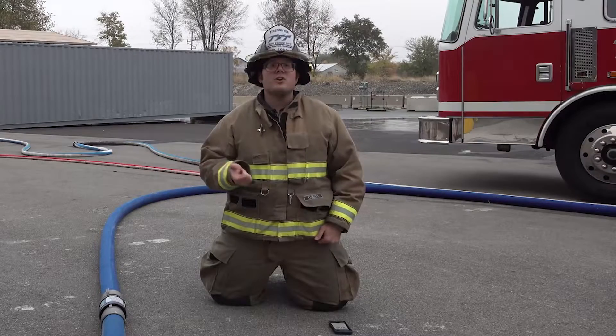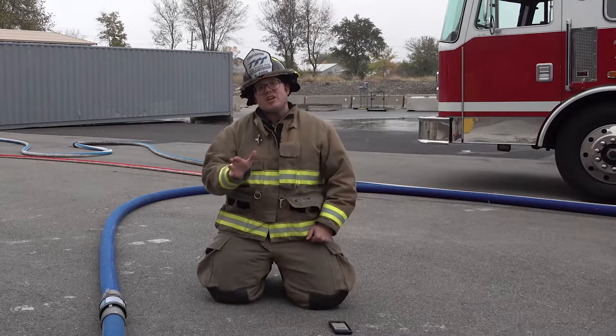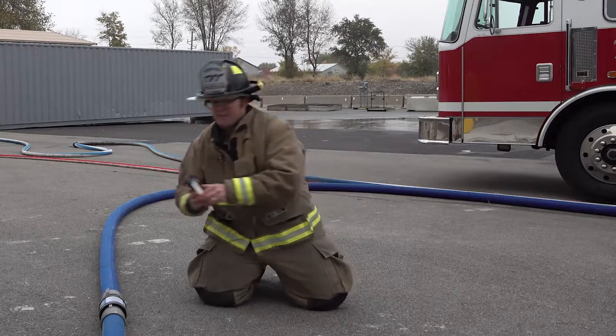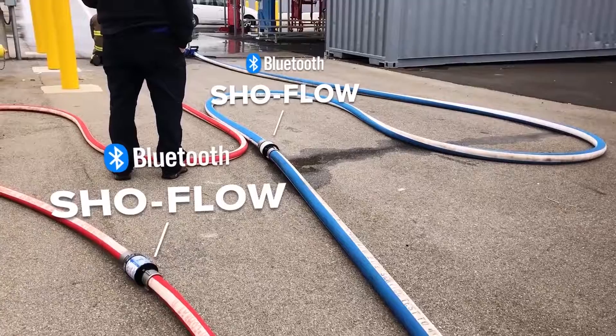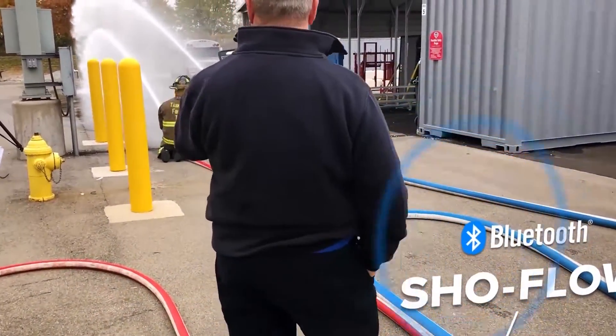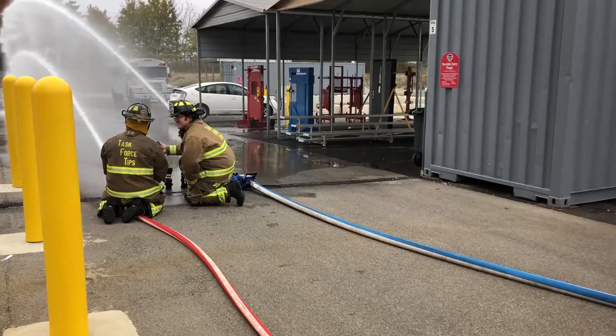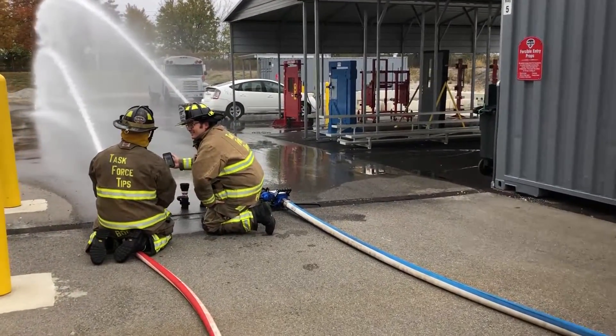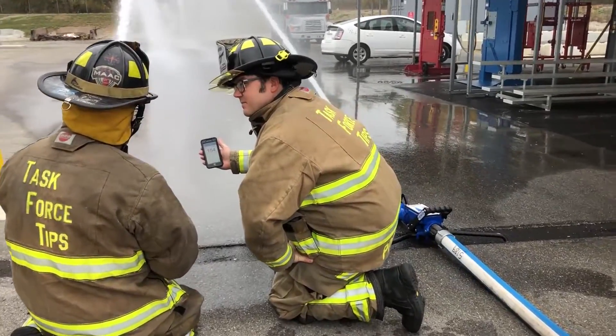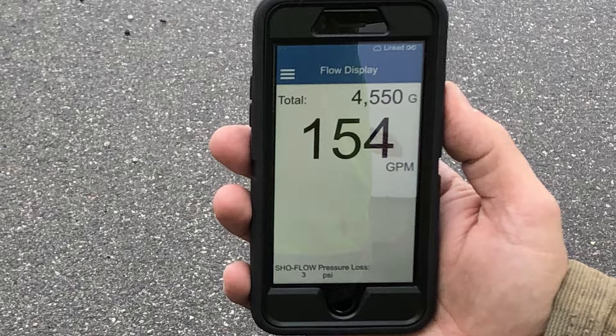The SHO-FLOW has an internal water-driven turbine that spins, and as it spins it generates enough power that you and your entire crew or training staff can connect your smartphone or tablet to the SHO-FLOW. You have the ability to read your flow rate, totalize so you can see the total amount of water delivered during that evolution, and see your friction loss of the flow meter — all in real time from your smart device.